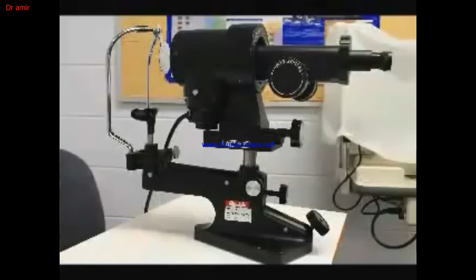Before taking a keratometry reading, the first thing that should be done is to focus the eyepiece. Position the white back occluder vertically in front of the instrument. Turn the eyepiece cap counterclockwise as far as possible. Looking into the eyepiece, turn it clockwise until the plus sign becomes sharp and in focus.